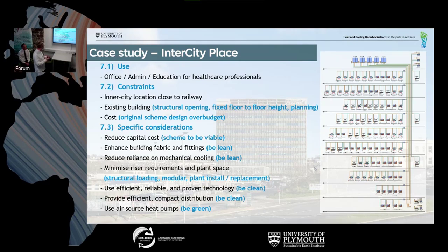This is kind of what led it towards an air source heat pump, because it was in a city - we didn't have water available to use a water source. Although Plymouth City Council have plans for an ambient loop network where we could have taken the heat from an ambient loop, and therefore water source would have been okay, we just don't have that available at the moment. The other important thing is it's near a railway, so we couldn't really drill close to a railway because they wouldn't like that vibration. The other thing was cost.